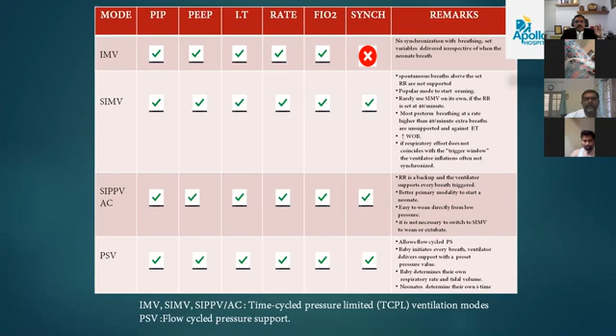SIMV: here the spontaneous breaths of the baby will be assisted, but you have to set the rate. Suppose you are setting a rate of around 60. So 60 breaths will be assisted by the ventilator. Every time the baby is breathing, the ventilator will sense it and assist the breath, and 60 breaths in a minute it will assist. Suppose the baby is breathing more than 60 times, around 70 or 80 times, the remaining breaths will not be assisted.